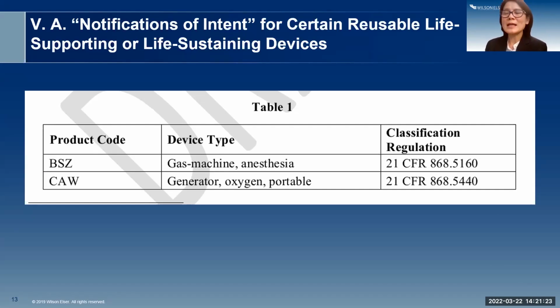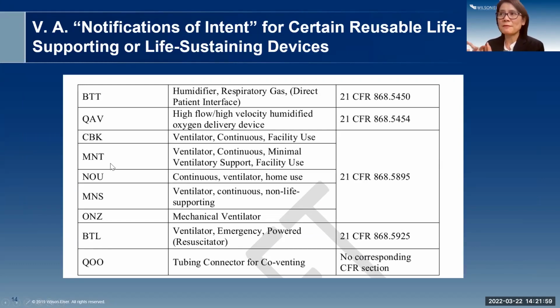The guidance document has a table, which I think is an exclusive, all-inclusive table. It lists the product code of all of the reusable, life-supporting, life-sustaining devices that the FDA expects you to file the notification of intent for. So you should look at the first, the left-hand column, product code. The products include some anesthesia gas machines, oxygen generators, respiratory gas humidifiers, and many types of ventilators, as well as tubing connectors for co-venting. So look at the product code. If your product falls under any of these codes, you should start filing a notification of intent as soon as possible.